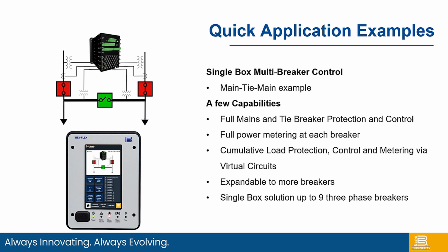Another example is, let's say, a main-tie-main application. In the main-tie-main application, this tiebreaker is going to be typically open, and these 2 sources are going to be feeding these 2 loads under normal states. With a main-tie-main, you have a tiebreaker, so if either of those sources is unhealthy, this tiebreaker will close, the other breaker will open, and therefore both loads will be fed by only one source.